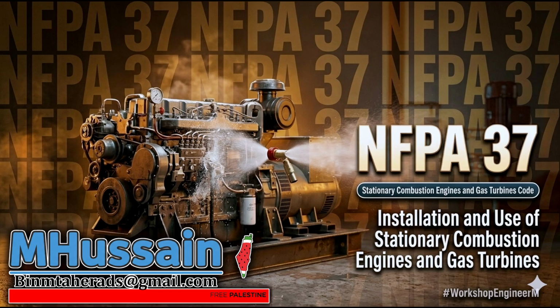Or at least move so much ambient air that the metal box doesn't get that hot. But what if the engine is off? Like a block heater shorts out at 2 a.m. That's the nightmare. The fan is off, the box is sealed, and it just bakes. The internal temperatures skyrocket. And the test doesn't know what the adjacent building is made of. The enclosure might max out at 400 degrees, but if the building next to it has foam insulation... It could melt or ignite. Yep. Exactly. So what's the actual advice for engineers here? Just fight the fire marshal?